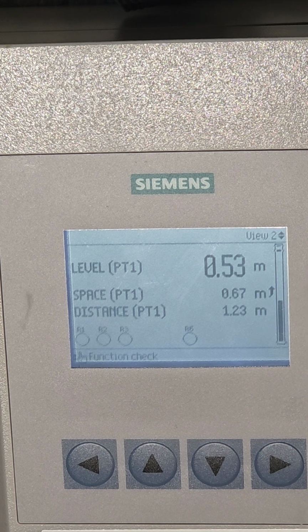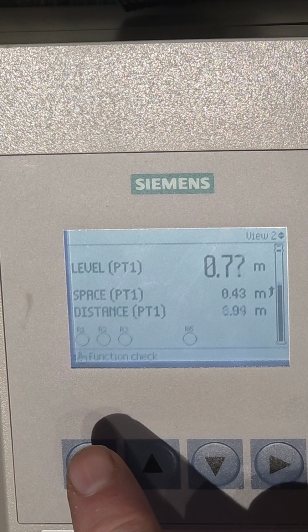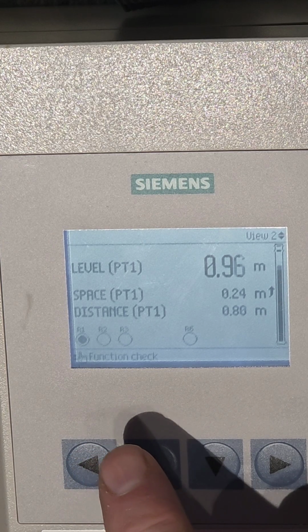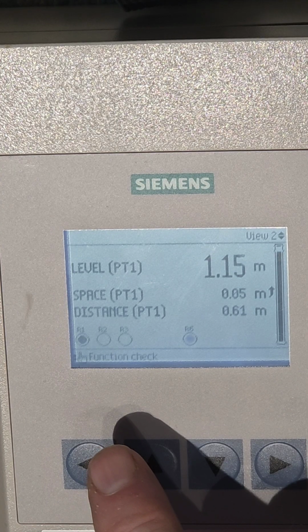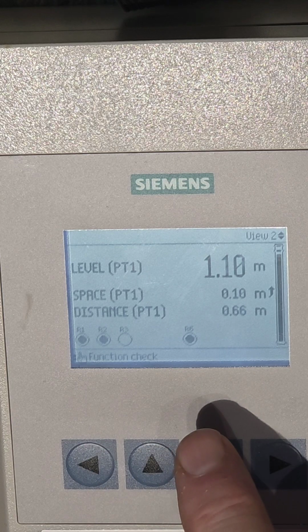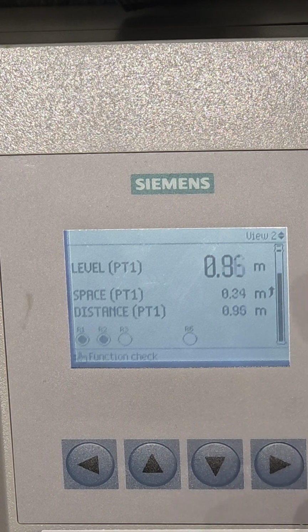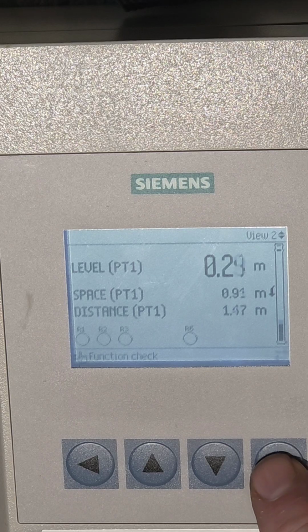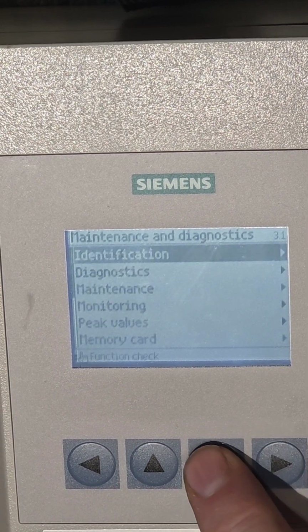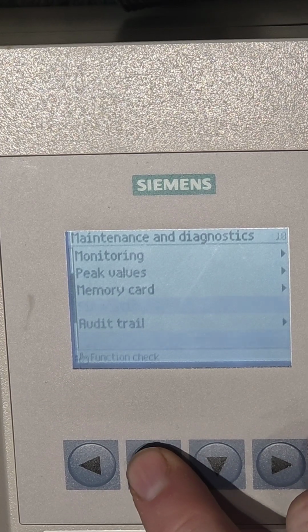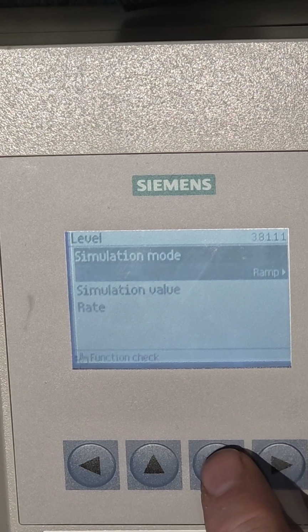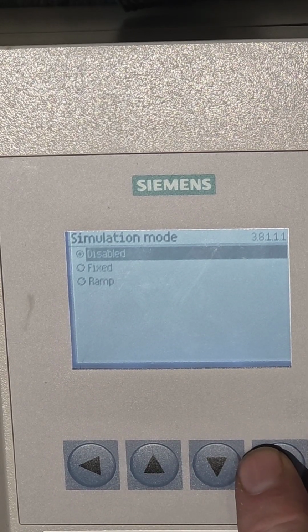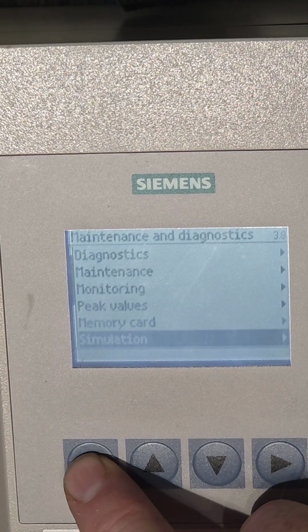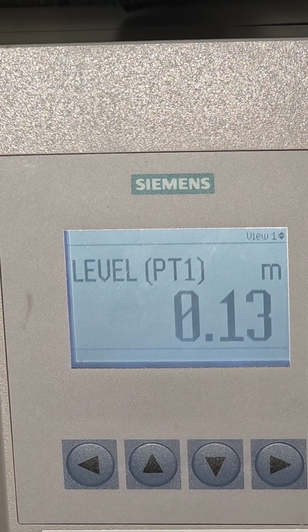It's now rising up here, so pump number 1 should come on at 0.8 meters. There it is. Pump number 2, there's pump number 2 on now, and the high level alarm. The high level alarm's off now because it's dropping down, and both these pumps should stop at 0.5 meters. There we are. Now you just need to come out of the simulation mode, right click, maintenance and diagnostics, all the way down to simulation, right click, process values, level, simulation mode, highlight disabled and enter, and then come right back out. That's it, reading the live value.